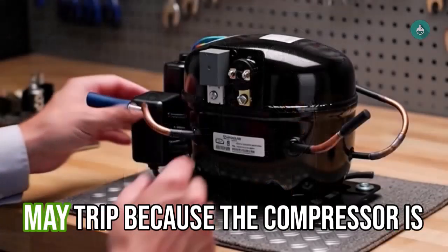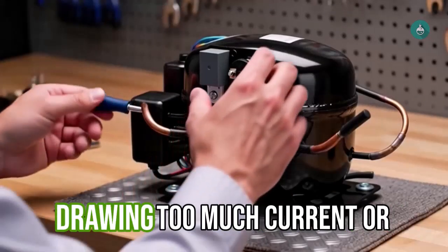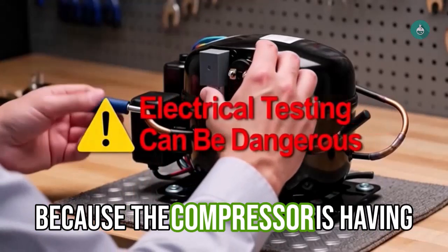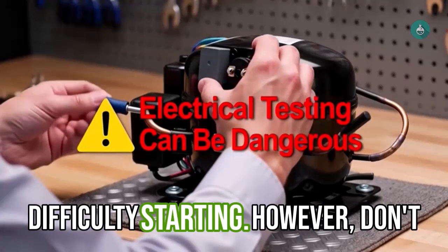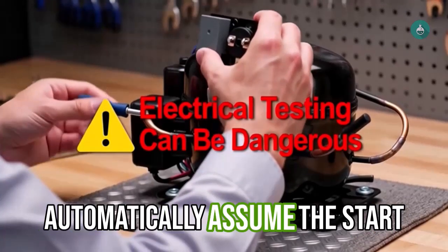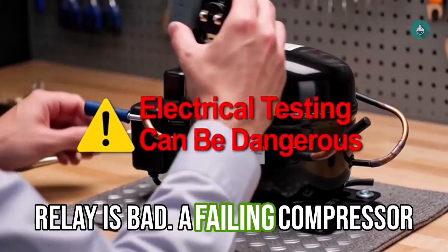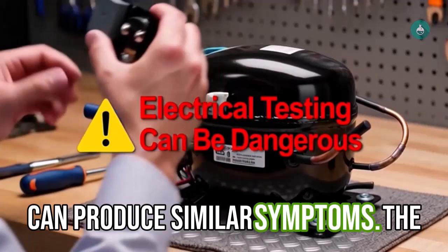The overload protector may trip because the compressor is drawing too much current or because the compressor is having difficulty starting. However, don't automatically assume the start relay is bad. A failing compressor can produce similar symptoms.